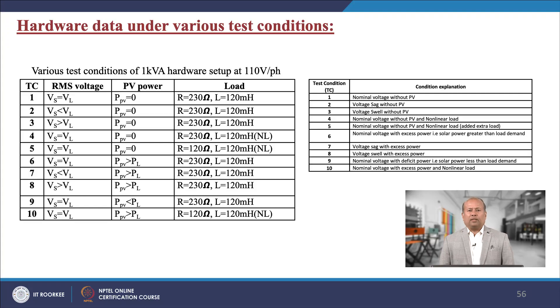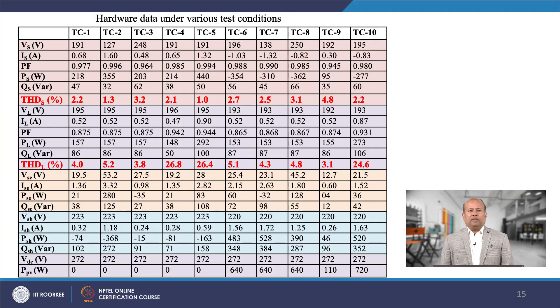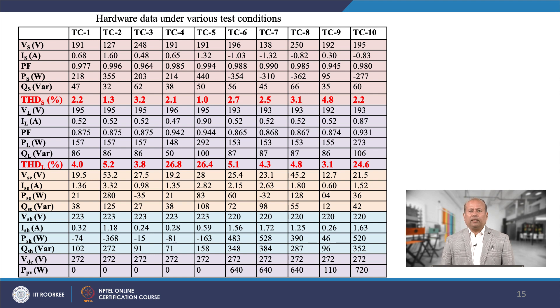Here, various test conditions of the hardware setup at 110 volt per phase are considered. For the above test conditions, various parameters such as voltage, current, power factor, real and reactive power, and THD are measured at the source side, load side, series and shunt side, as well as towards the DC link side. These are tabulated clearly, and from the table we can observe the behavior of the proposed system under various test conditions.